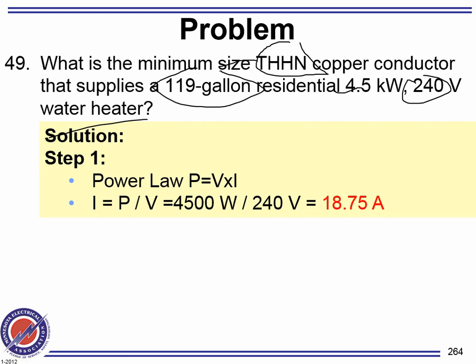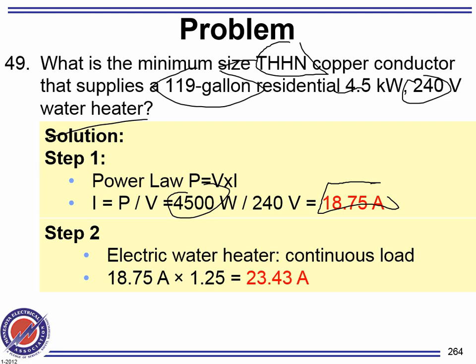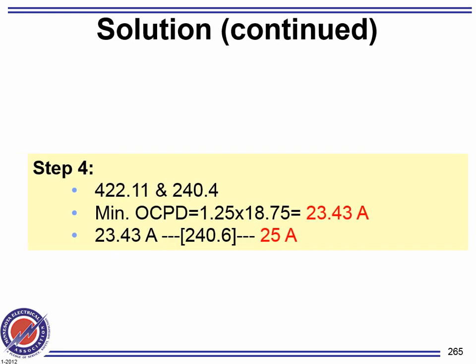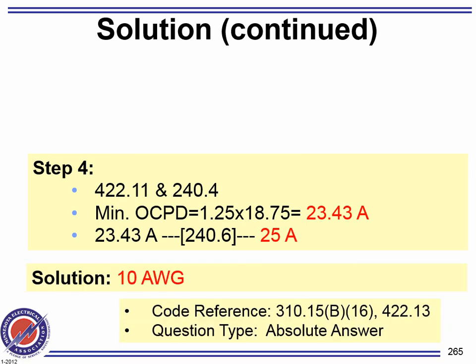So I have 4.5 kW. It's a water heater, so the power factor is 1. And here's my amps. If that was a non-continuous load, guys, you're done, and you go size your conductor. But since it's a continuous load, what do we do? Up it 25%, that'll get you 23.4, and then your conductor will be based on 23.4, and your breaker will be 25. Your breaker will be 25.